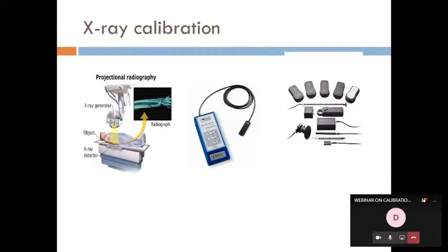You need to electronically test the X-ray machine. This is the process of calibrating the X-ray with a dosimeter. Where will you calibrate the X-ray? On the door side, everywhere. You place the dosimeter near the machine, and you can also place a dosimeter outside the X-ray room. If there is any scatter radiation, that can also be measured with the help of a dosimeter.